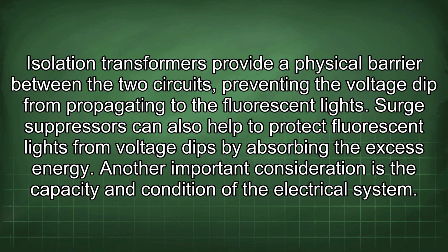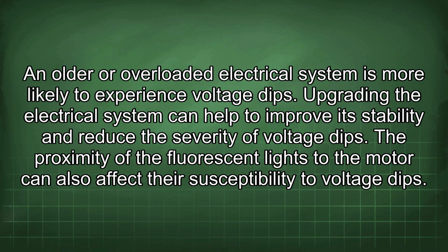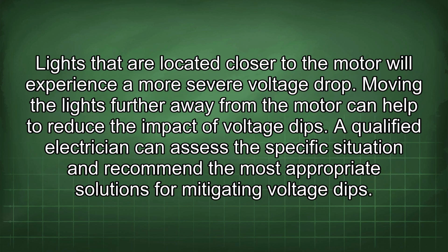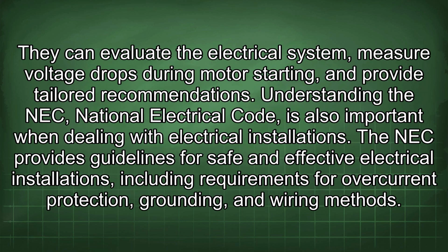Another important consideration is the capacity and condition of the electrical system. An older or overloaded electrical system is more likely to experience voltage dips. Upgrading the electrical system can help to improve its stability and reduce the severity of voltage dips. The proximity of the fluorescent lights to the motor can also affect their susceptibility to voltage dips. Lights that are located closer to the motor will experience a more severe voltage drop. Moving the lights further away from the motor can help to reduce the impact of voltage dips. A qualified electrician can assess the specific situation and recommend the most appropriate solutions for mitigating voltage dips. They can evaluate the electrical system, measure voltage drops during motor starting, and provide tailored recommendations.